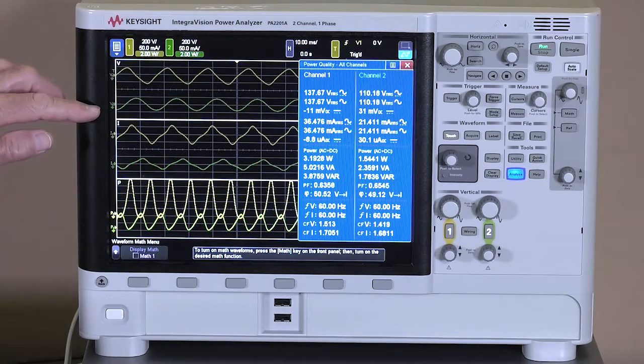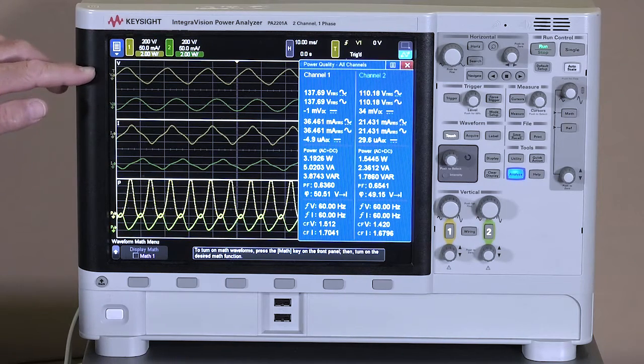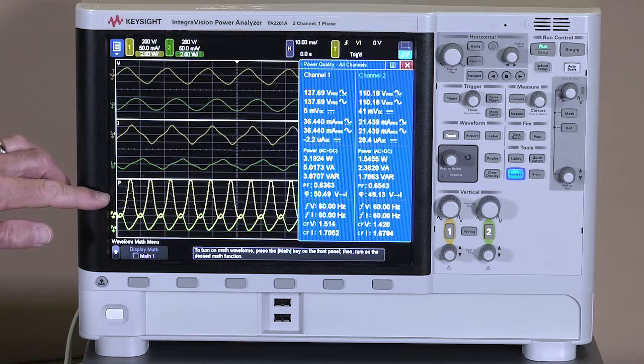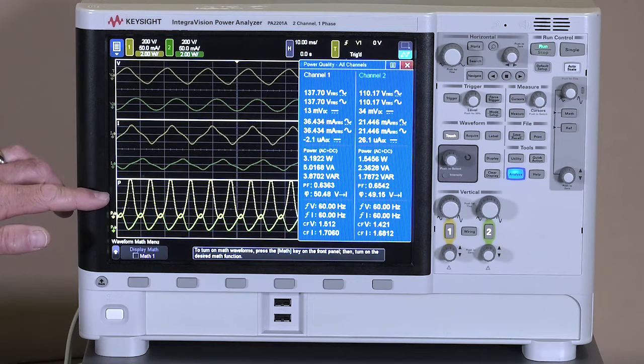So now we're putting our 110 volts across the other coil, and as you can see, our yellow coil has slightly higher voltage, slightly higher current, and has the much higher power. So now it's doing most of the work while the motor is turning in the opposite direction.